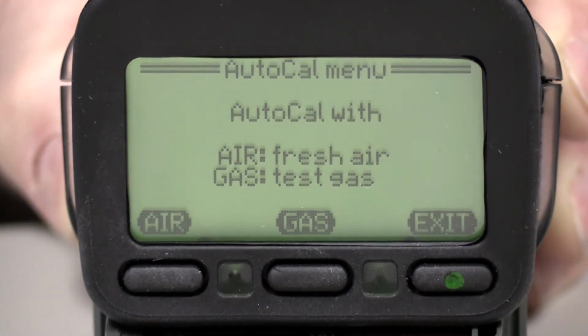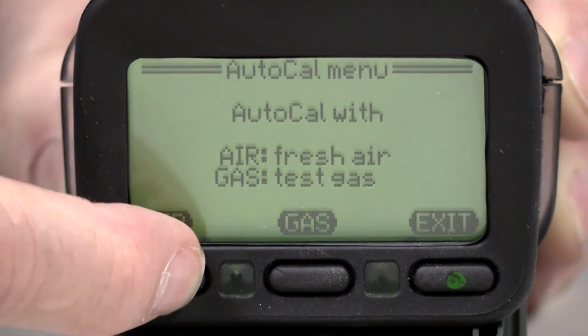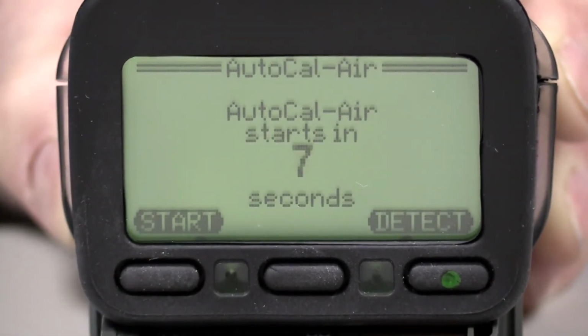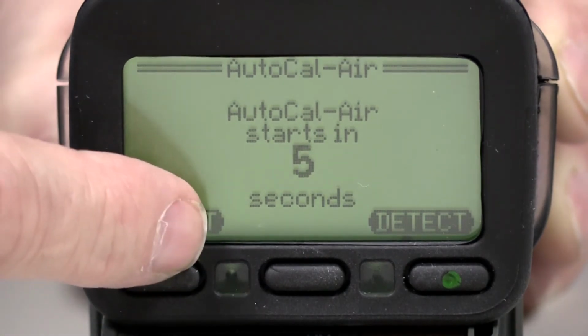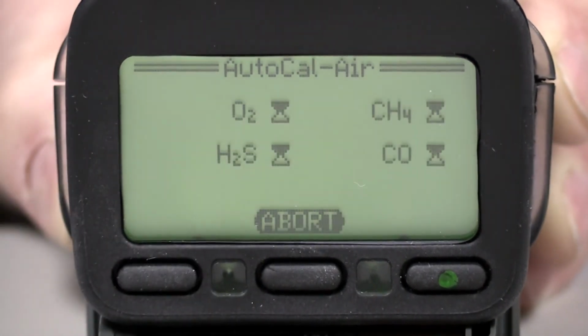Press air to start the autocal fresh air adjustment procedure. After pushing the air button, the instrument will count down the remaining seconds before beginning the adjustment. You can press the air button again to begin the adjustment immediately, or you can wait for the countdown to end and for the instrument to automatically proceed. Pressing abort ends the autocal procedure without completing the adjustment.